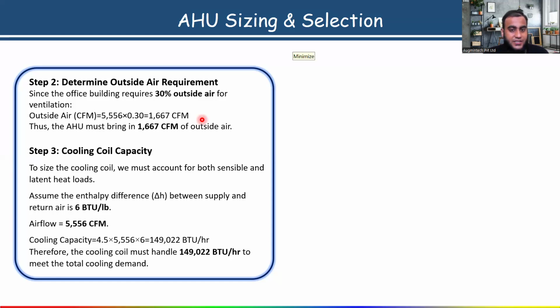Yeah, Sayyid Kasif, I have explained while calculating the airflow, we only have to consider the sensible heat load. Why? Because airflow directly impacts the temperature changes in a space, na? And that is a function of sensible heat. So we have to consider the sensible heat load. We don't need to add latent heat load here while calculating the airflow, because latent heat is related to removal of moisture. In case of cooling coil capacity, when you are calculating, at that time you have to take both sensible and latent heat. But here, I have only taken the sensible airflow rate. Is it clear? Okay.